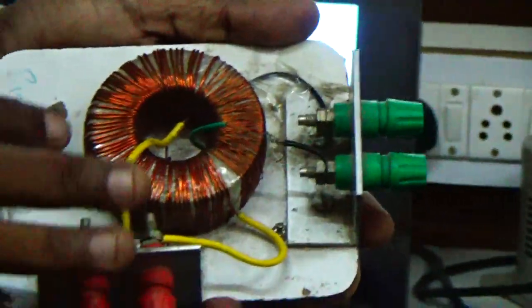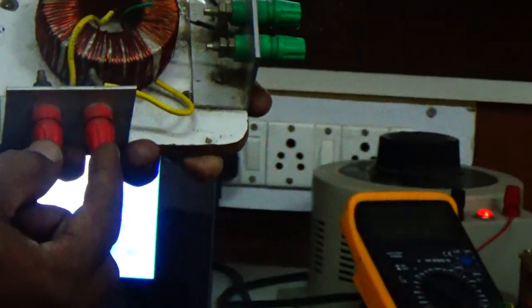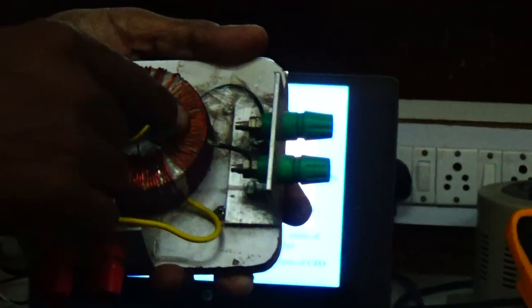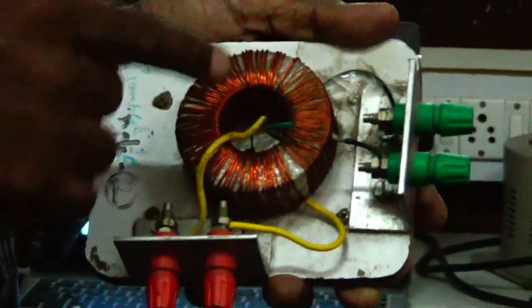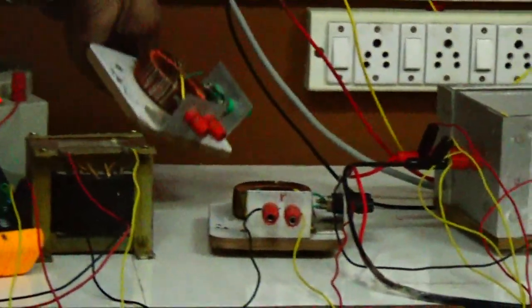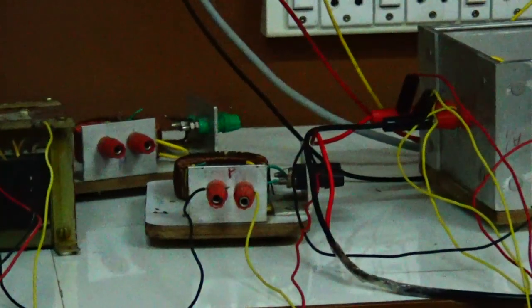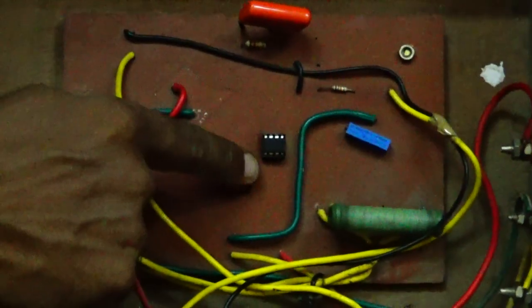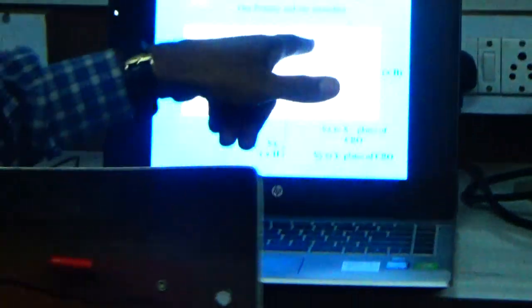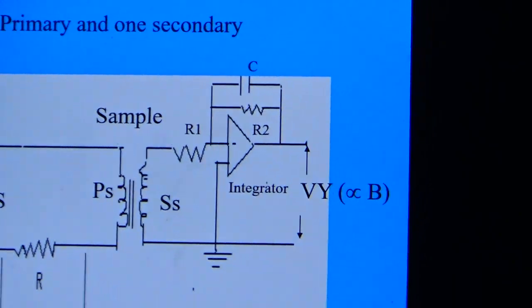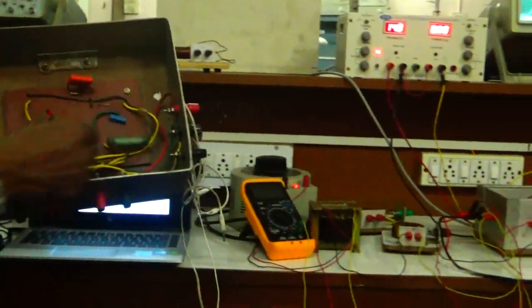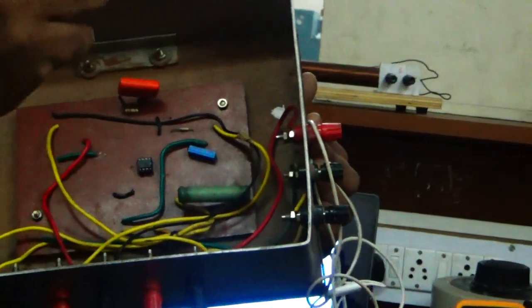So this is mounted on a platform, so that the voltage coming from the step down transformer can be fed to the primary coil, and the EMF which is induced in the secondary coil due to the magnetic induction that is developed inside the material can be tapped across the secondary terminals. These secondary terminals, as you can see, are now fed to a circuit which consists of an integrator, and you can see that you have an operational amplifier, and using an RC circuit that is shown in this diagram, proportional to one cycle of the input signal, we can measure the proportional integral output of the B.